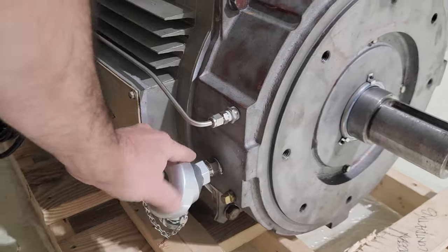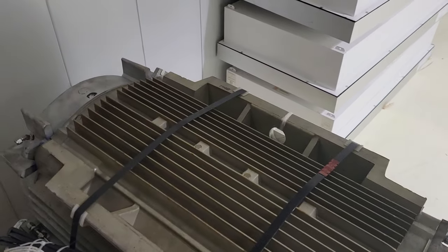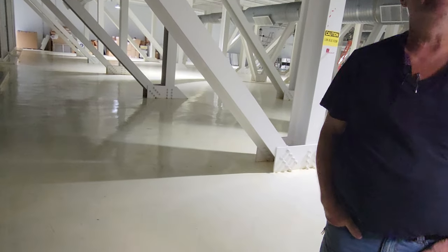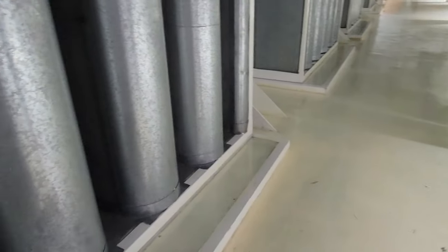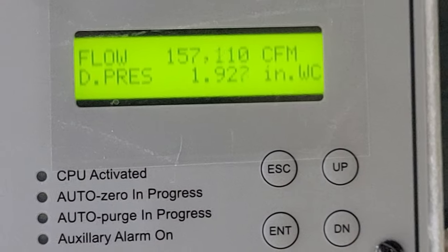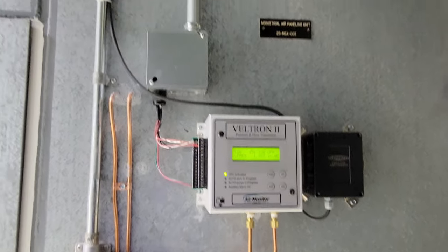What's this thing here — just a collector? That is oil. And we also have vibration sensors on these so we can check the bearings. We have a vibration monitor that attaches to all of that. So these are for noise, that's the reason we got this. It's all one belt, all one power, but they can actually be pitched — that's how you speed it up or slow it down instead of speeding the motor up. Once they're set they're done. Adjusted for 155,000 CFM per fan and we're running a 1.9 static, times 6, because we're running 6 fans — at 155,000 CFM per fan.